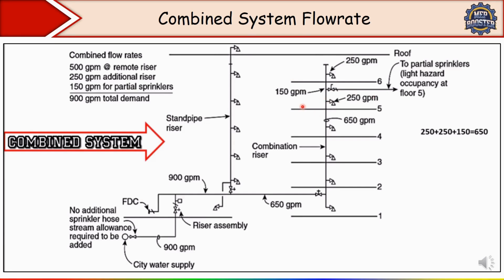at this floor number 5, let's say, okay, because I have discussed this point already, if you remember, that 150 GPM for partial sprinkler, okay. So here in the given diagram, 150 GPM is allocated for partial sprinkler at floor 5, which suggests that sprinklers are installed only in a specific high-risk area such as a storage room, electrical room or corridor. The rest of the floor may rely on the standpipe system for manual firefighting, okay. This is common in light hazard occupancy where the fire load is low and full sprinkler coverage may not be required by code, okay.